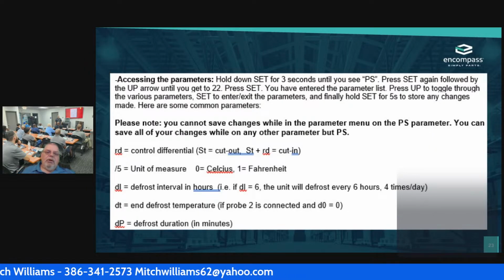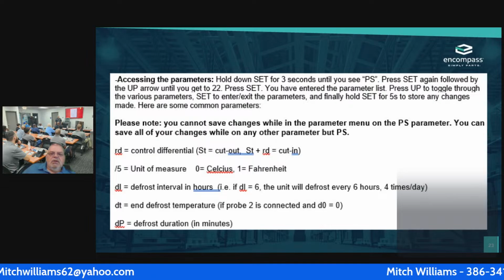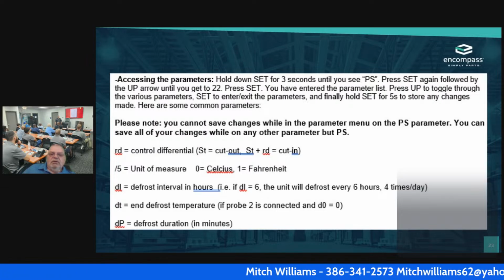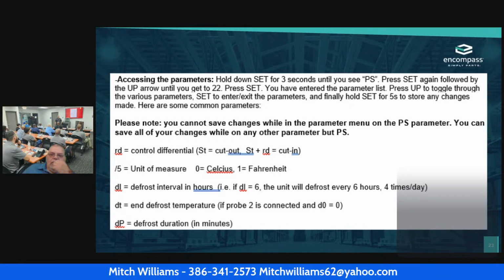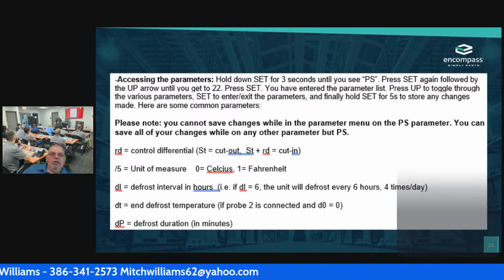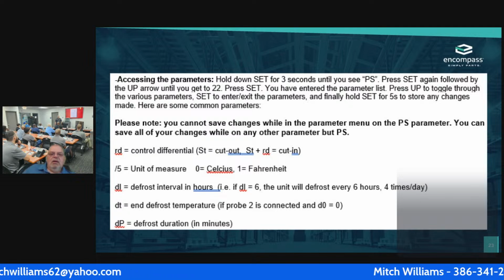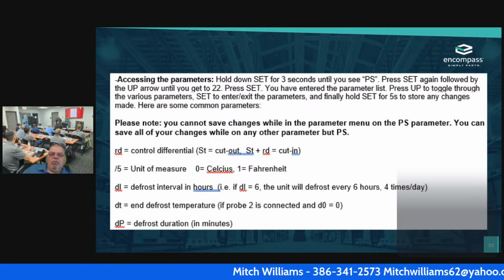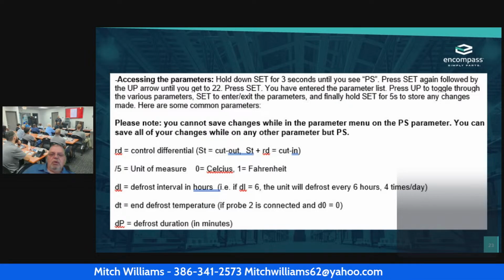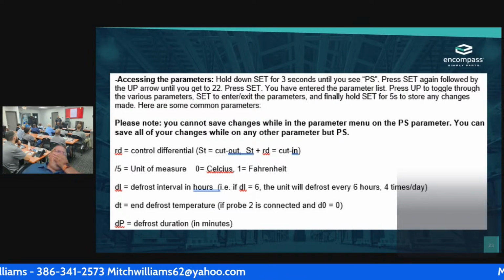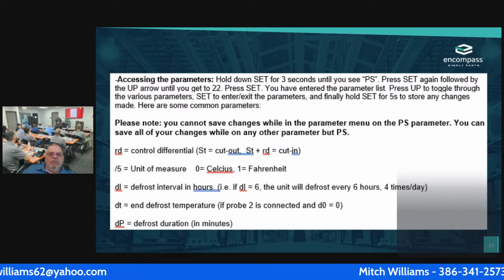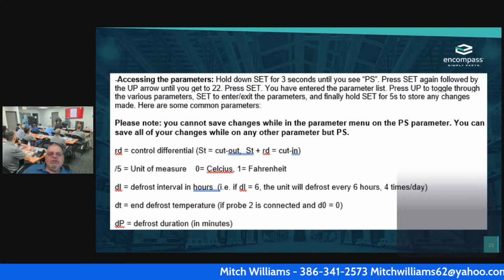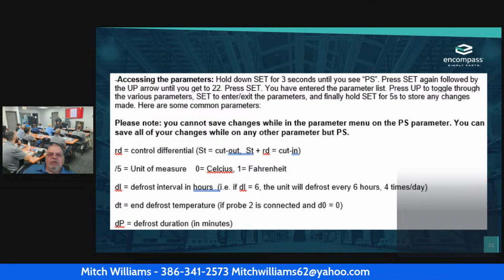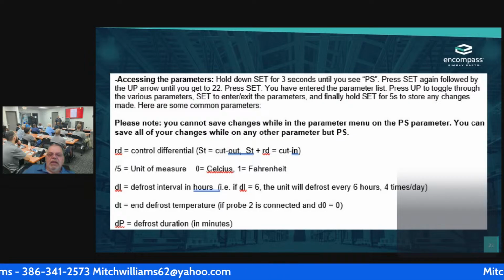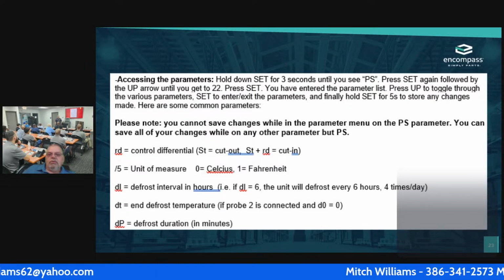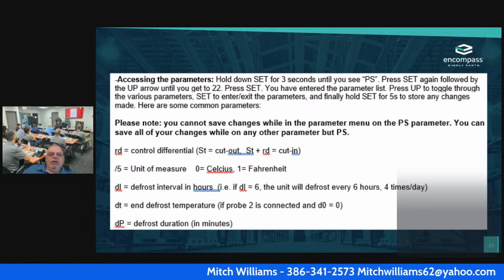Okay. Accessing the parameters. Once again, we kind of went through this. I'm going to hold the set point down for 3 seconds until you see a PS. Okay. Then press the set again, followed by the up arrow until you get to 22. Okay. Now I've entered into the parameter list. Then I'm going to press up to toggle through the various parameters. To set, I'm going to hit set/enter. Enter/exit the parameters, and finally hold the set for 5 seconds to store any of the changes that I make.